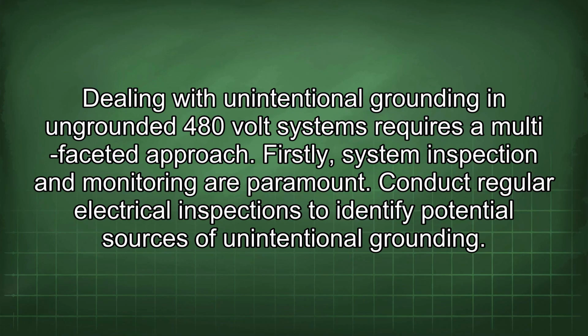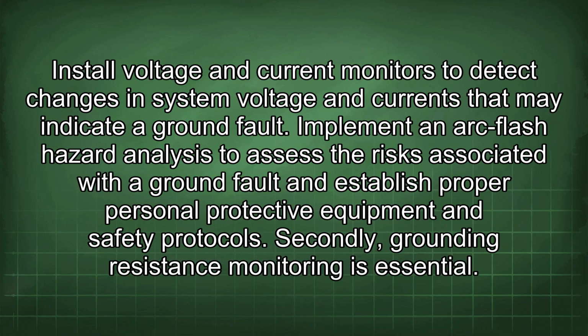Dealing with unintentional grounding in ungrounded 480-volt systems requires a multifaceted approach. Firstly, system inspection and monitoring are paramount. Conduct regular electrical inspections to identify potential sources of unintentional grounding. Install voltage and current monitors to detect changes in system voltage and currents that may indicate a ground fault.